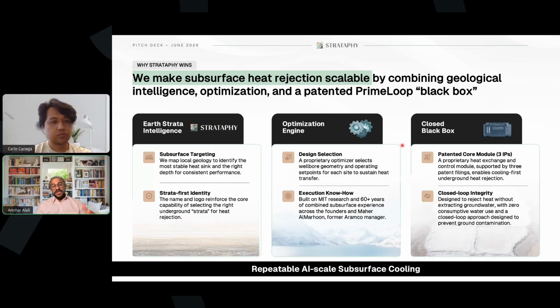The same applies underground, and we need to model that over a long period. If my system runs with this load profile, is it fixed, or does it change month to month? What is the thermal buildup underground, and how does it impact system performance? That determines the design of the downhole system - the depth, how many wells you need, and their horizontal distribution.